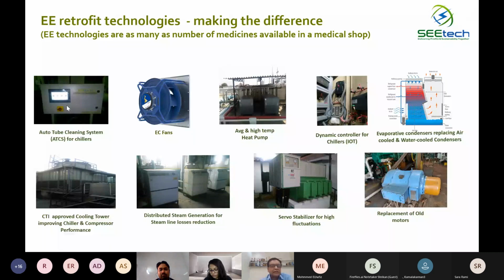So this is a continuous cleaning system. By doing this, a resultant saving of almost 4% to 10% has been seen in the chillers. Then we have listed their EC fans. In the EC fan, you'll find that the motor and the fan are all in one simple assembly. There is no belt drive, so you're not losing anything. And then there is an option for speed control also in the same assembly.